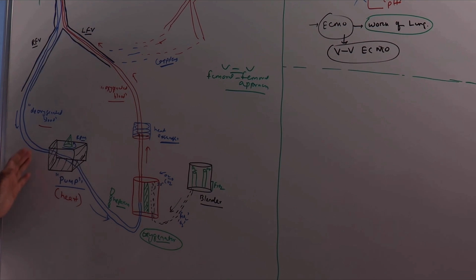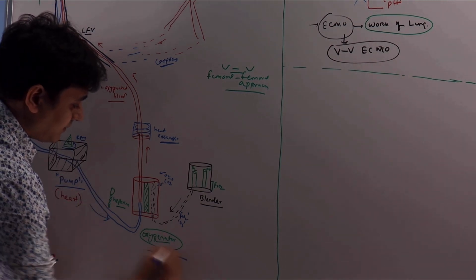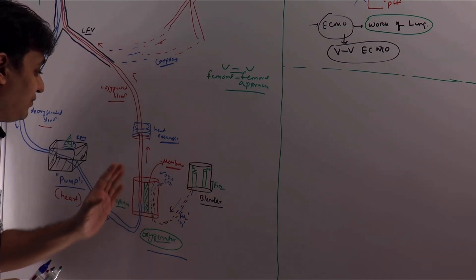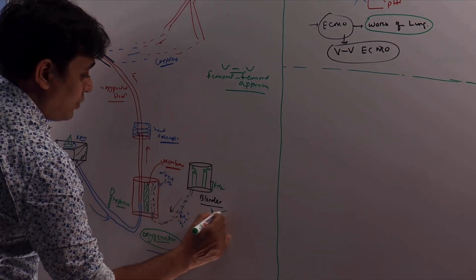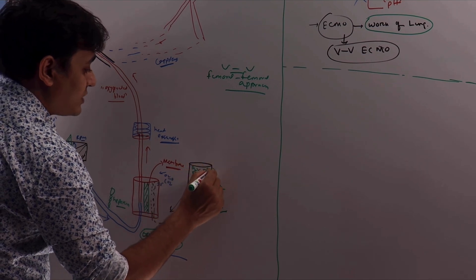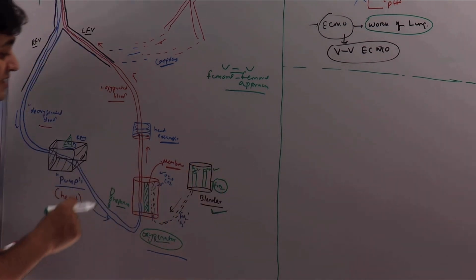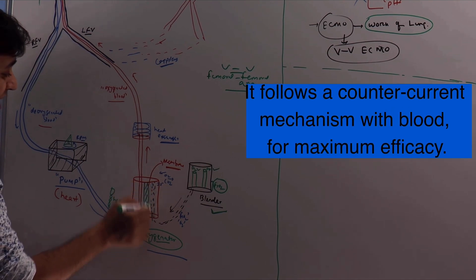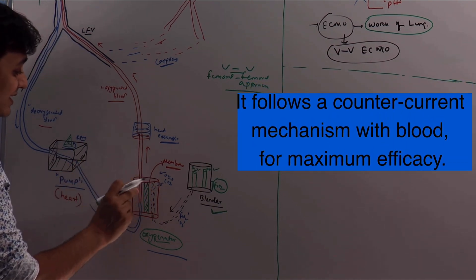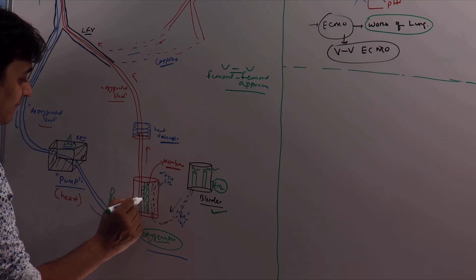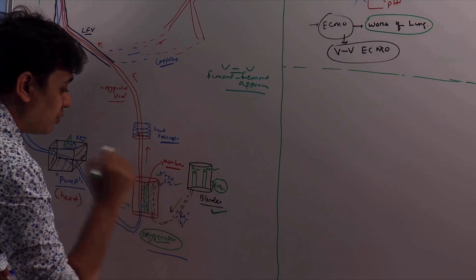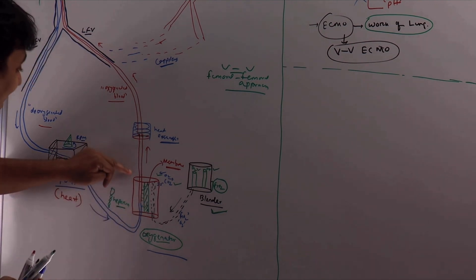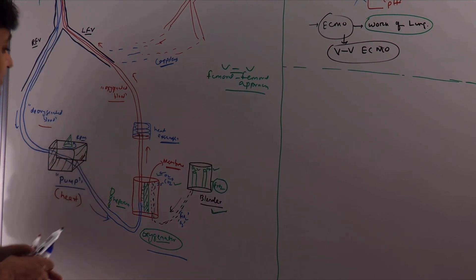The principal function of the lung is oxygenation and carbon dioxide removal, so there is another machine through which the blood must pass — that is called the oxygenator. The oxygenator contains a membrane through which diffusion of oxygen and carbon dioxide takes place. There is a blender with air supply and oxygen supply that determines the FiO₂ to deliver. Oxygen travels through the oxygenator while blood also travels through it, so gas exchange happens: carbon dioxide is removed and oxygen is put into the blood. The dark deoxygenated blood enters the oxygenator and bright red oxygenated blood comes out.